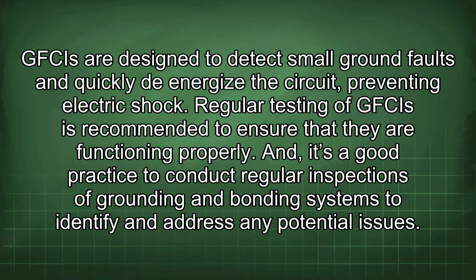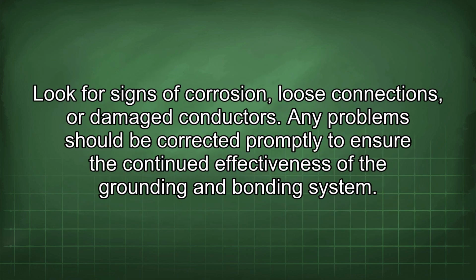And it's a good practice to conduct regular inspections of grounding and bonding systems to identify and address any potential issues. Look for signs of corrosion, loose connections, or damaged conductors. Any problems should be corrected promptly to ensure the continued effectiveness of the grounding and bonding system.